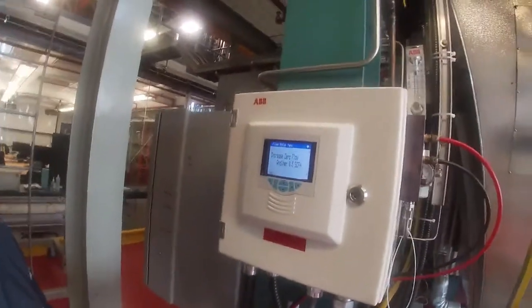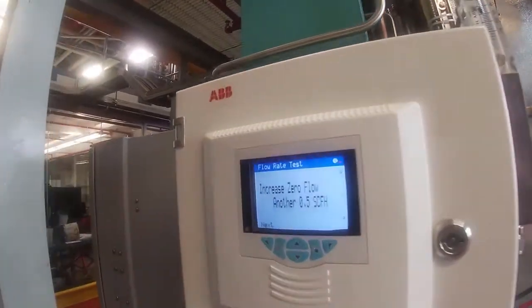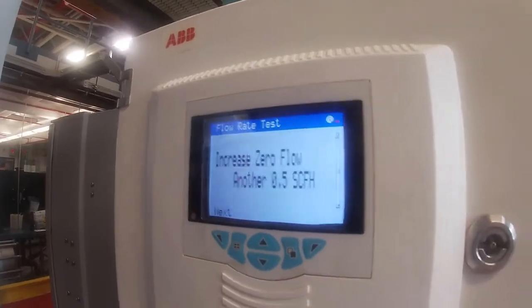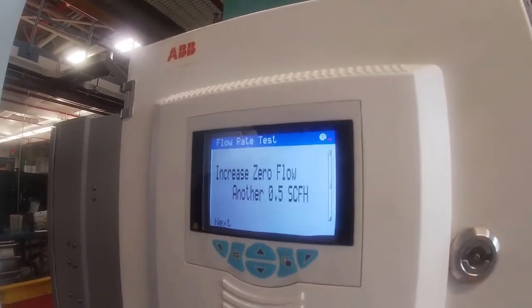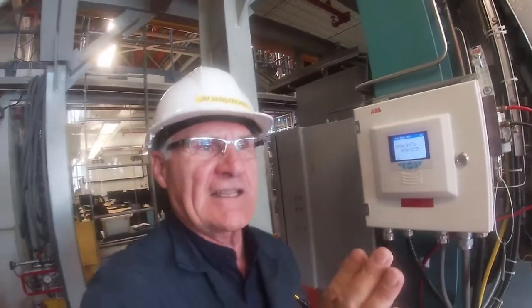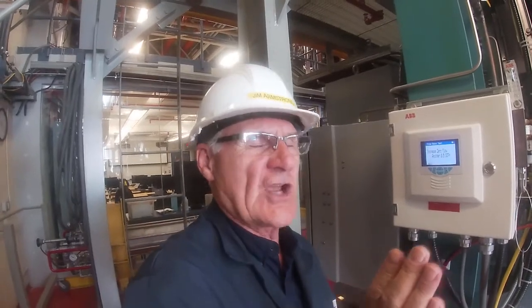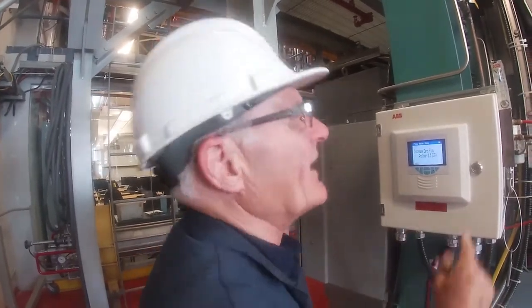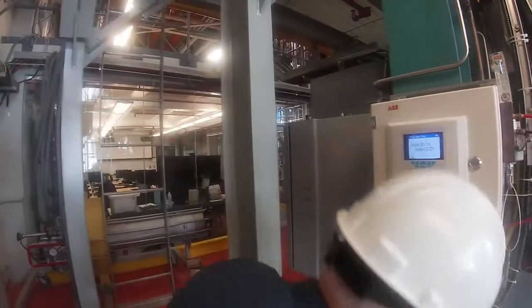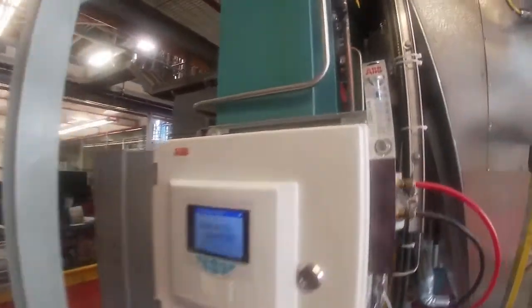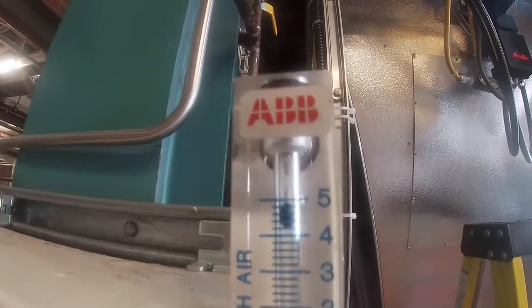Next key says increase the flow another 0.5 cubic foot. So we found the point where the test gas we're injecting is just overcoming the sample gas, and now it's telling me to put another 0.5 cubic foot on it. I'm going to take it up to 4.5, and that's what we're going to run.